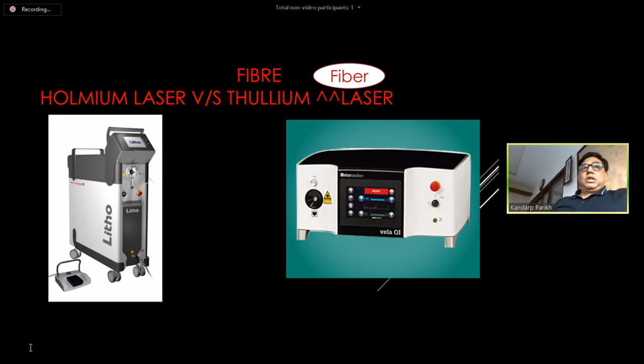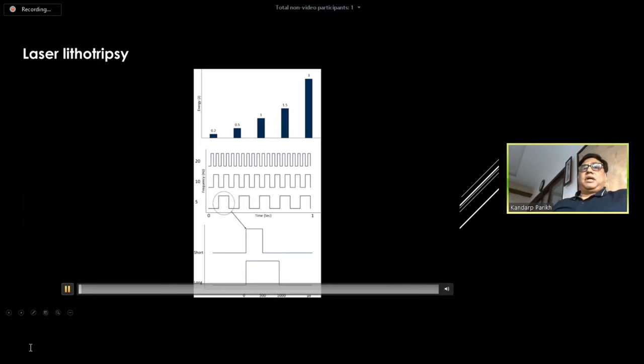thulium fiber laser. There are three important parameters of a holmium laser machine, and that is, one is the pulse energy, second is the pulse frequency, and third is the pulse duration. Now, depending upon the type of the machine, you can have a pulse energy setting. Pulse energy may range from 0.3 to 6 joules, depending upon if it's a low power machine or a high power machine. In a low power machine, you can go up to 2 joules. Pulse energy is the optical energy which is emitted from the tip of the laser fiber with every pulse, and which is measured in joules.